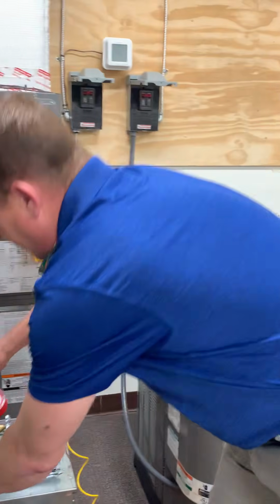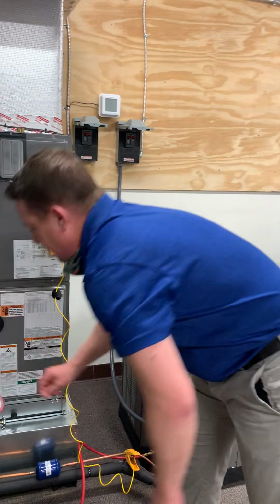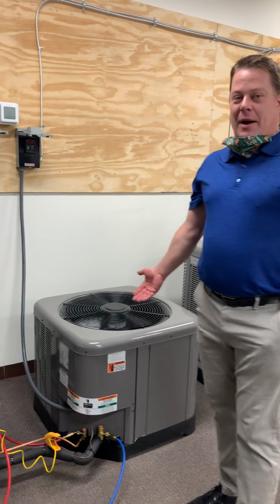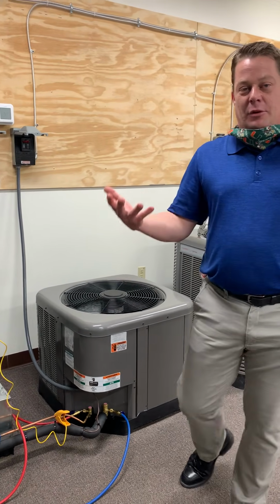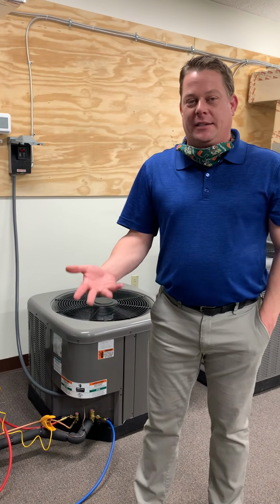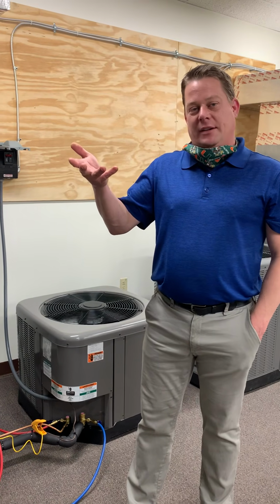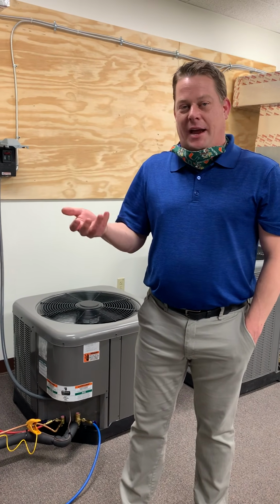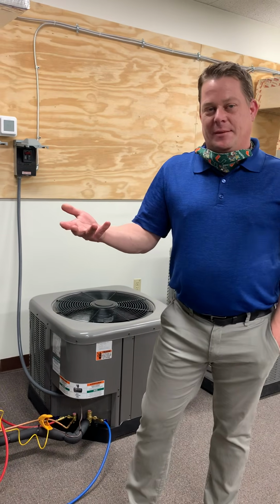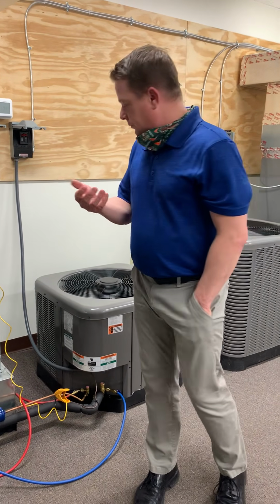Now I can refer to the manufacturer specification and determine if my charge is right. If my subcooling's low, I would add refrigerant to bring it up. If my subcooling's high, I would take some out to bring it down to try to get into the manufacturer specification.